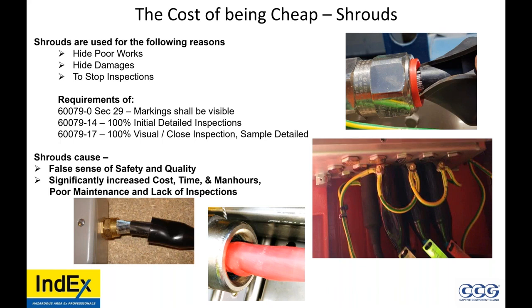When you're installing them, I've seen many people forget to put the gland shroud on, so they take the cable gland off the cable. The more you rework something, the more horrible it is. The armor of the cable or the outer insulation or inner insulation now becomes more depressed, maybe cold flow going on, because people are opening and closing the gland. Shrouds have no benefit besides to those who want to hide their poor quality work, damages, or stop inspections. They're a great tool for hiding all that.